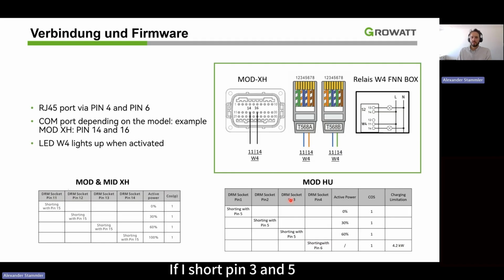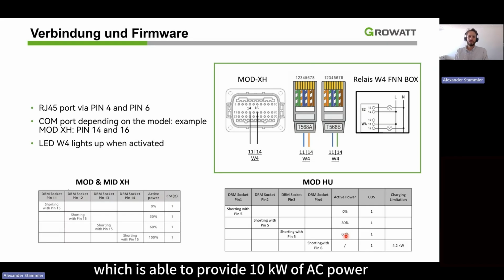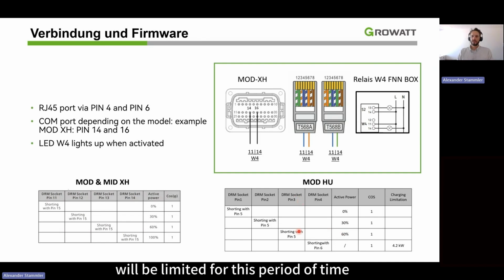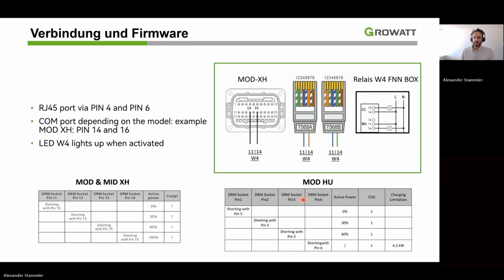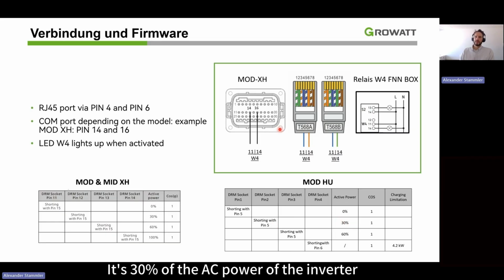If I short pin 3 and 5, so here 3 and 5, then the AC output power of the inverter will be limited to 60%. So if you have a 10 kW inverter, which is able to provide 10 kilowatt of AC power, and we short circuit pin 3 and pin 5, then the AC power will be limited to 6 kilowatt. It's not the export power that will be limited, it's the AC power of the inverter that will be limited for this period of time. The same is here with pin 2 and 5. It's 30% of the AC power of the inverter.